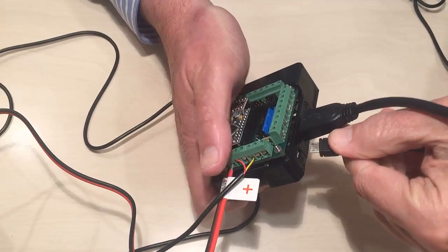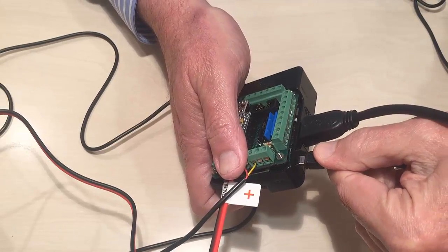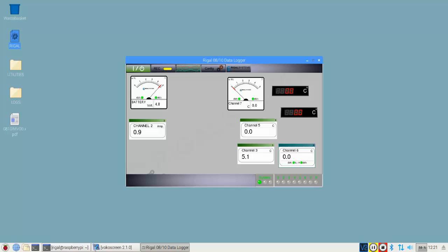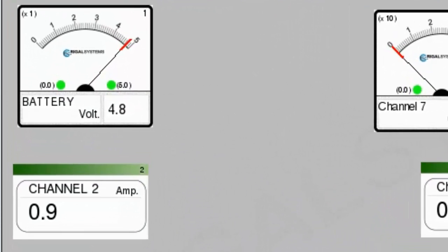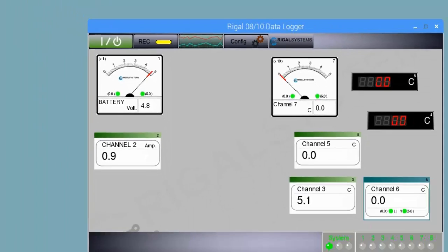We screw the terminals in place and the sensor is connected. Now we plug in the Rigal, and once the display screen appears, channel 2 shows a measurement corresponding to the signal sent by the sensor. Don't worry if the number doesn't make much sense yet, since we still need to configure the sensor according to its characteristics. Right now the number shown is close to 0, even though the room isn't at 0 degrees.